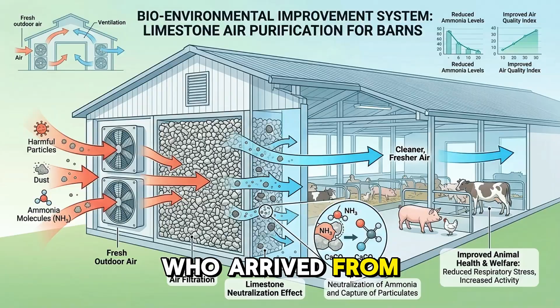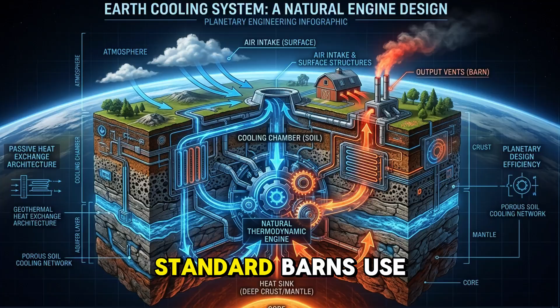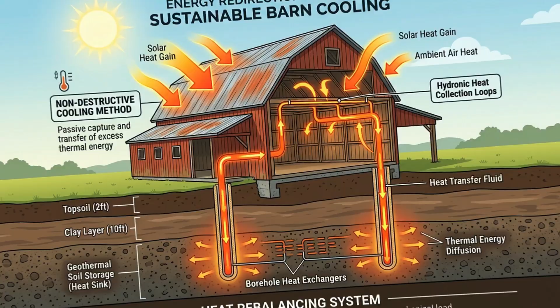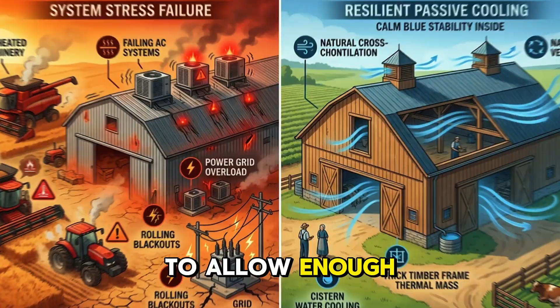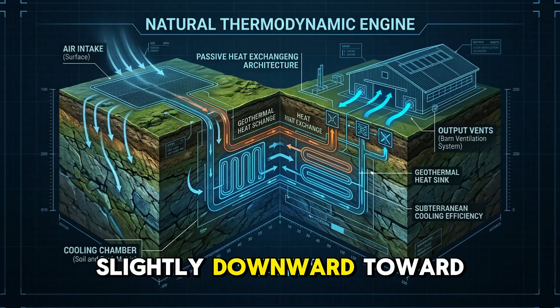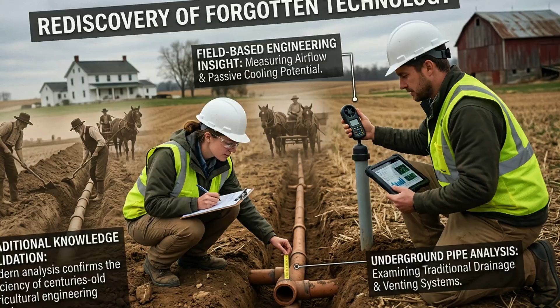The design remains almost absurdly simple. The trench stays six feet deep because that is where temperatures stabilize. Standard barns use an eight inch pipe. Larger structures scale to twelve inches. The pipe runs at least 100 feet underground to allow enough contact time between air and soil. The trench slopes slightly downward toward the building, so condensation drains properly instead of pooling inside the pipe. That alone creates remarkable cooling.